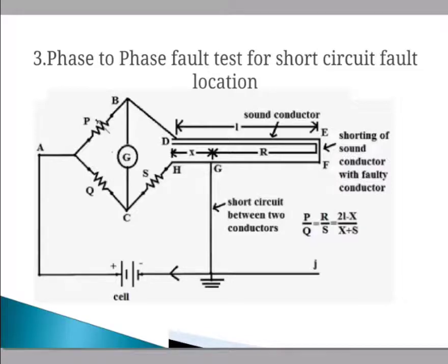Similarly, testing between the two cables, if short circuited, will indicate a 0 reading, as already discussed. If there is sufficient insulation, it will indicate some value. If the conductor is earthed, then testing between the conductor and earth will show less resistance in comparison to a sound conductor.